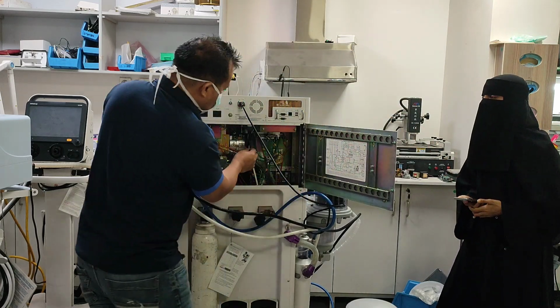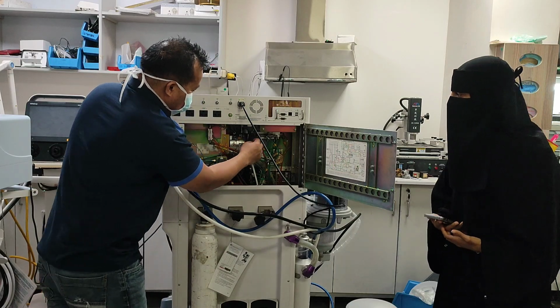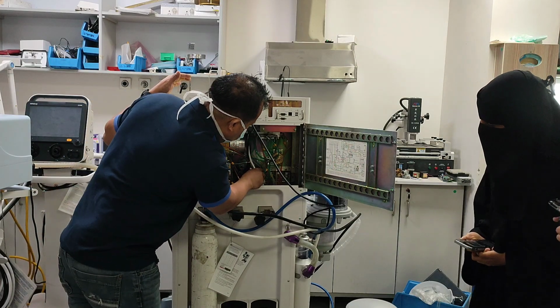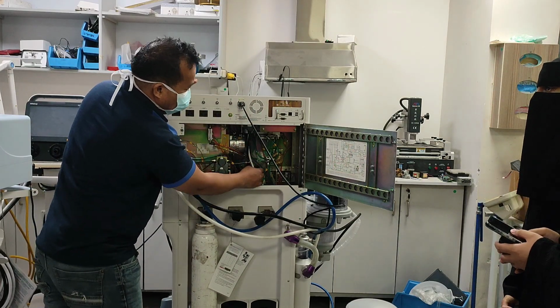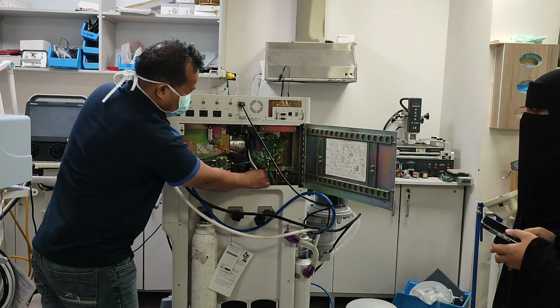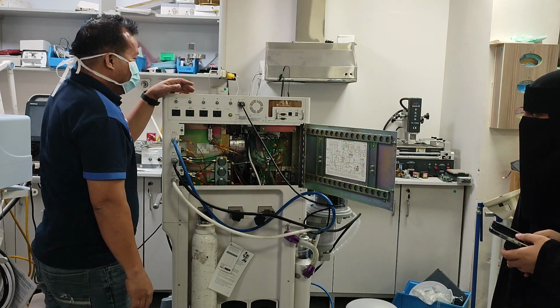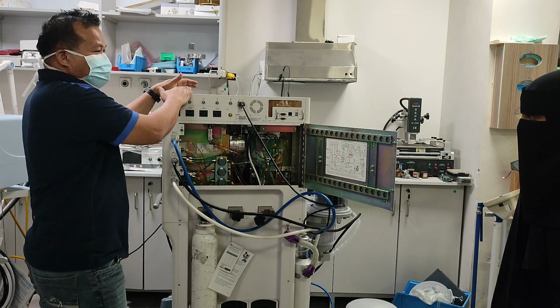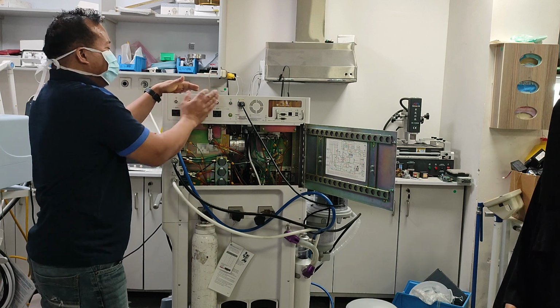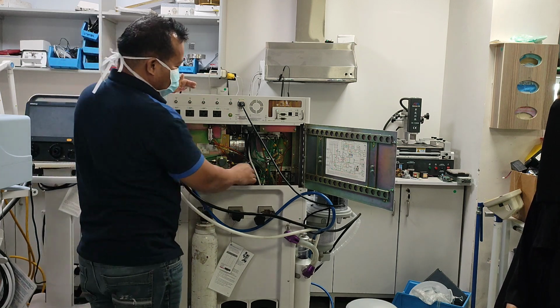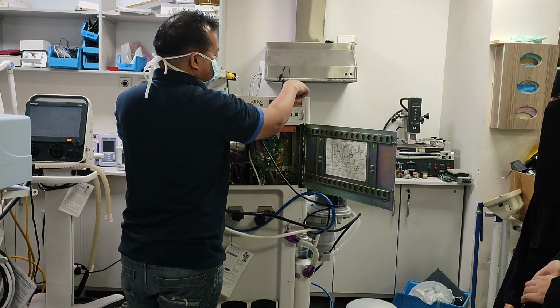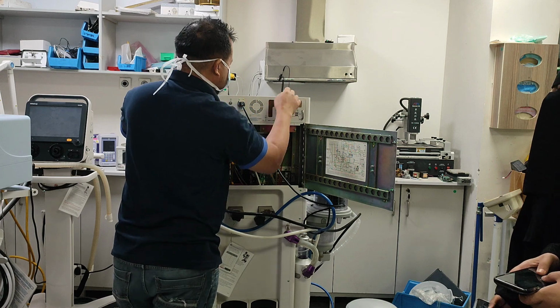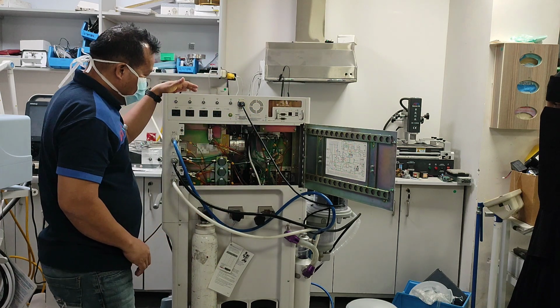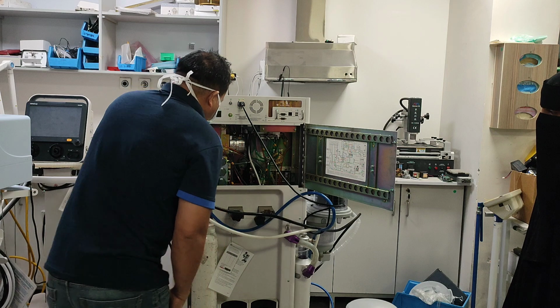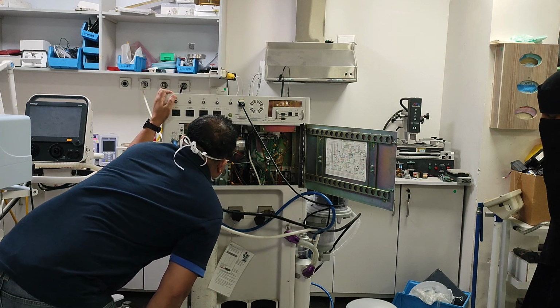If you see the cable here, it is going to the display. So if there is an issue with the display, where there is no display on the screen but the ventilator is running, you should check this wire and where it goes. This is the CPU board. It's like a computer.